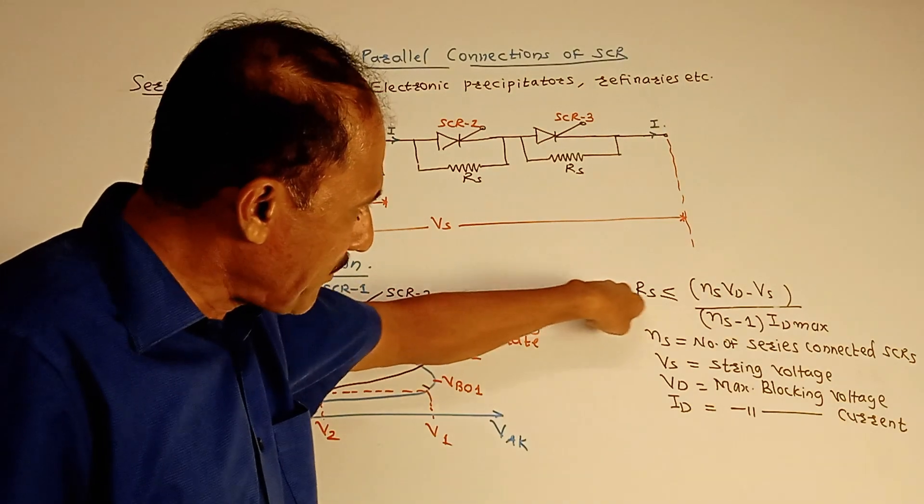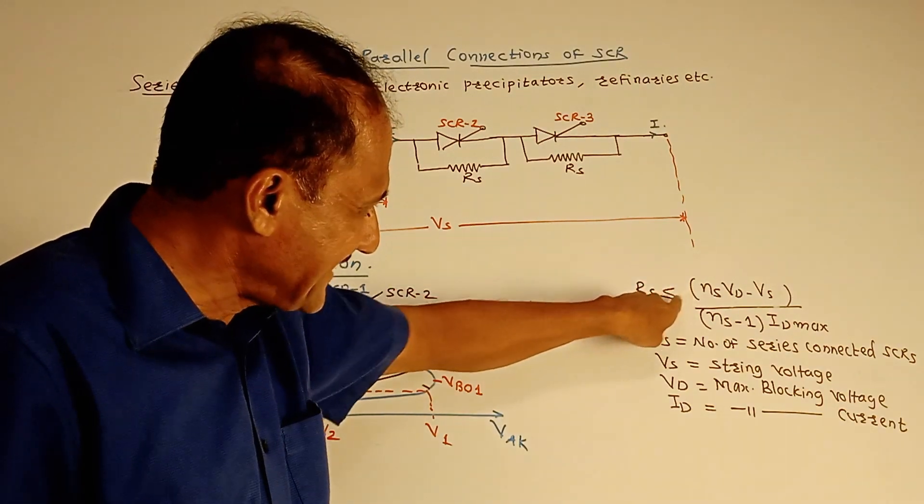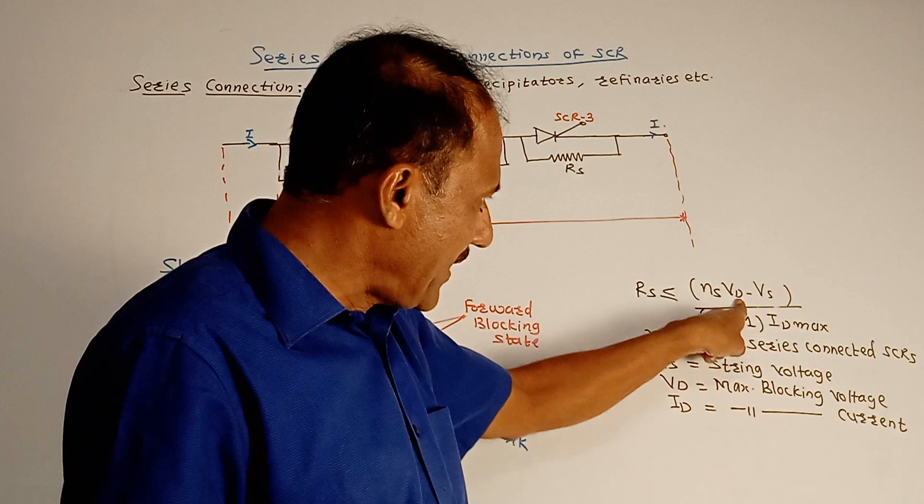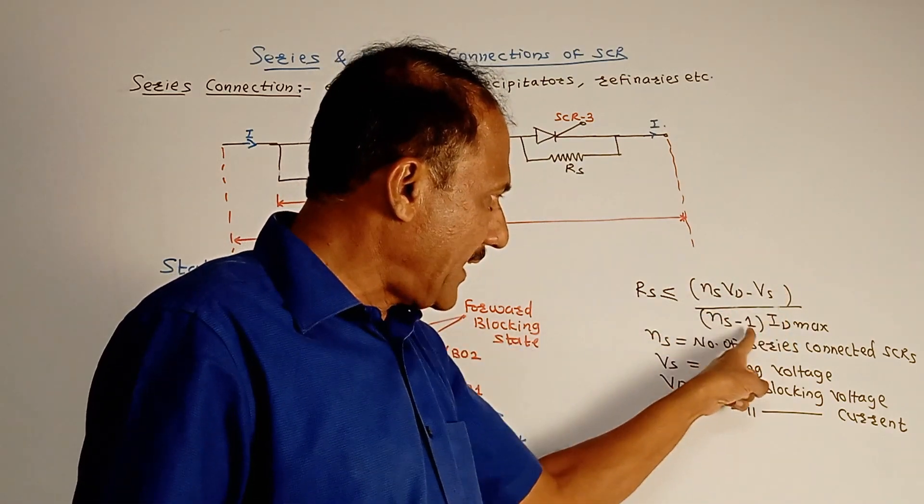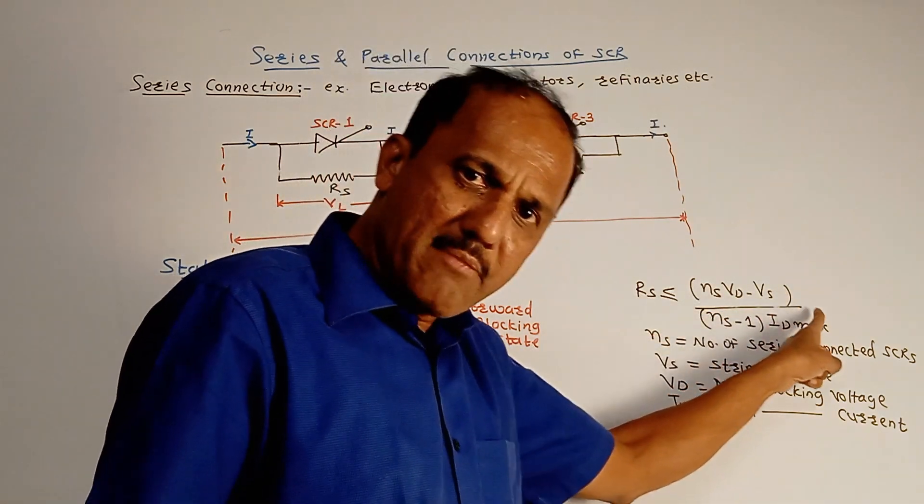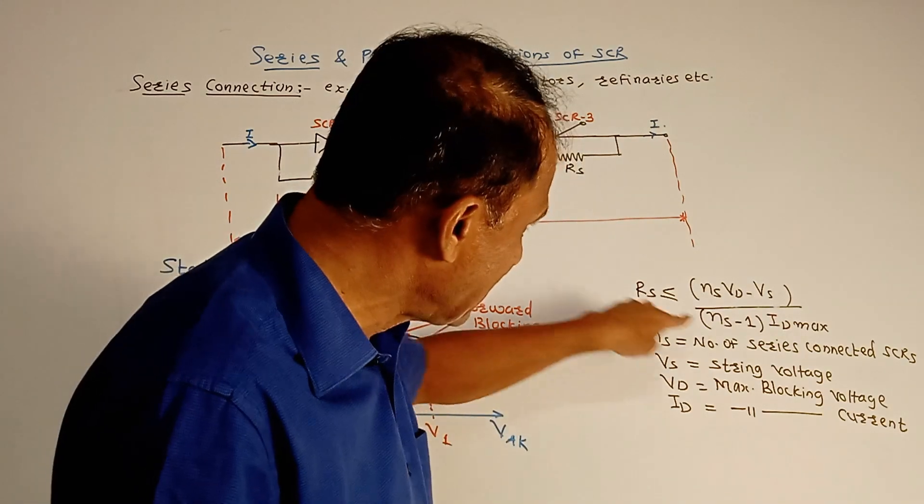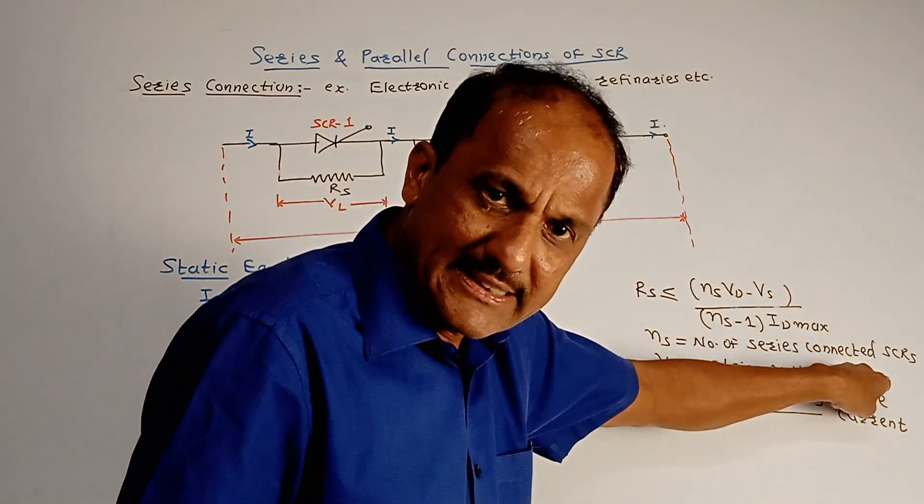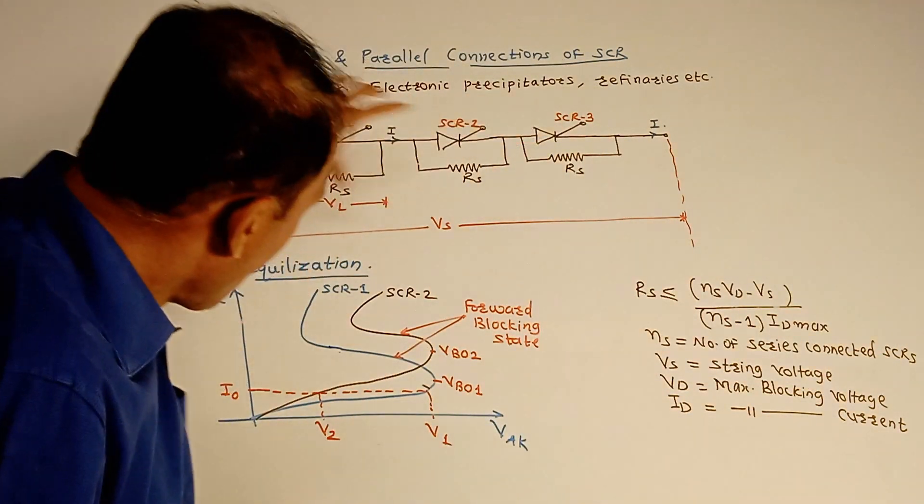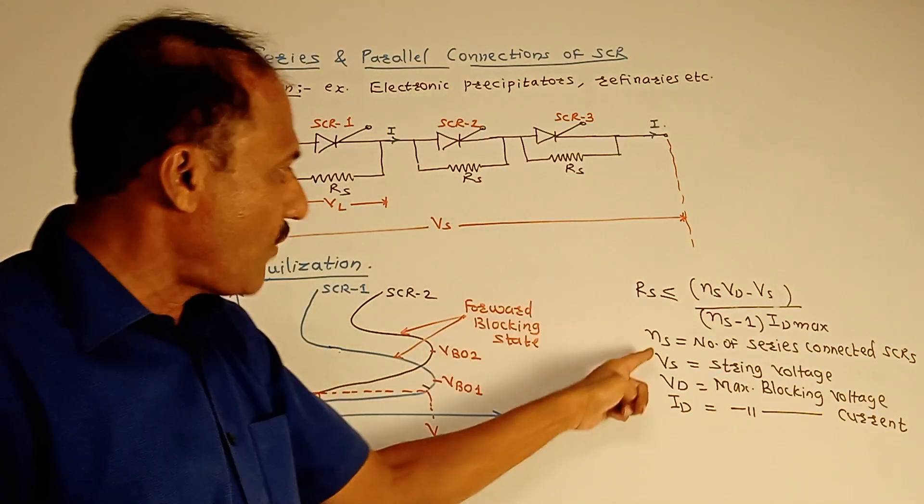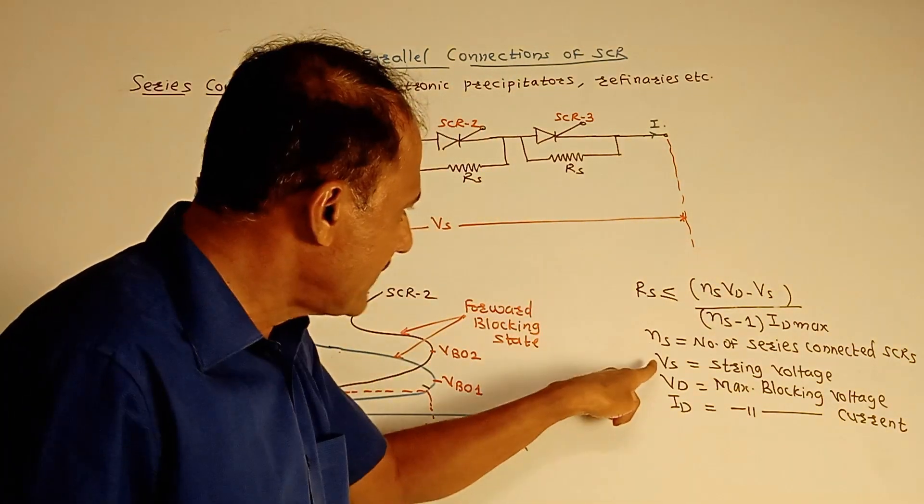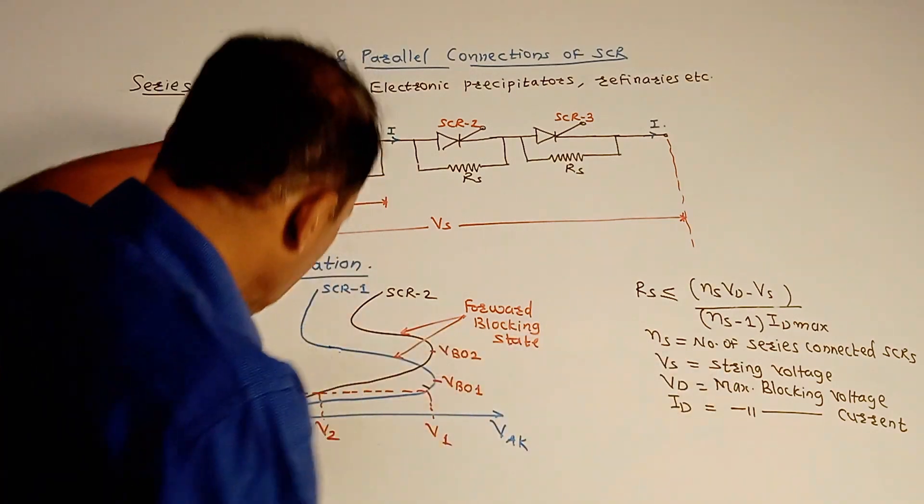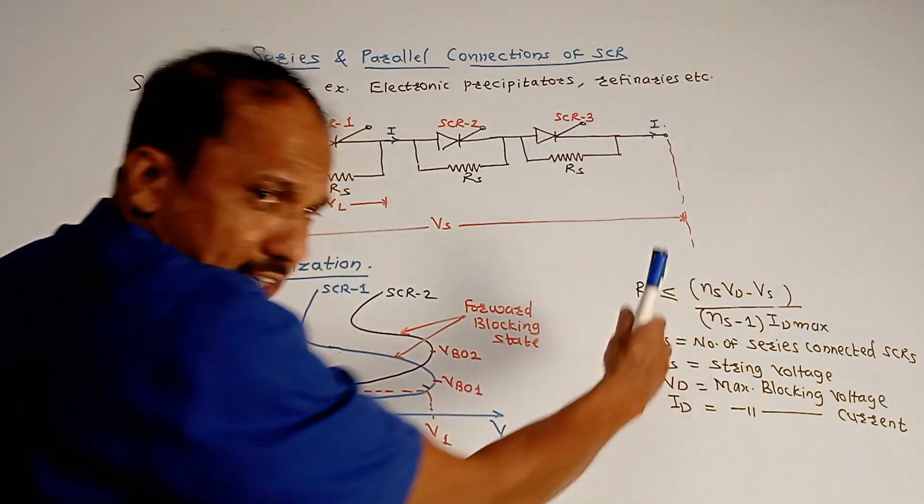Now this value of resistance Rs, which is used to obtain the static equalization, is approximately given as: it is less than or equals to Ns times Vd minus Vs upon Ns minus 1 into Id max, where Ns means number of series connected SCRs. Just say in this diagram, the value of Ns will be three. Then Vs is the string voltage, just now I explained, total series combination.